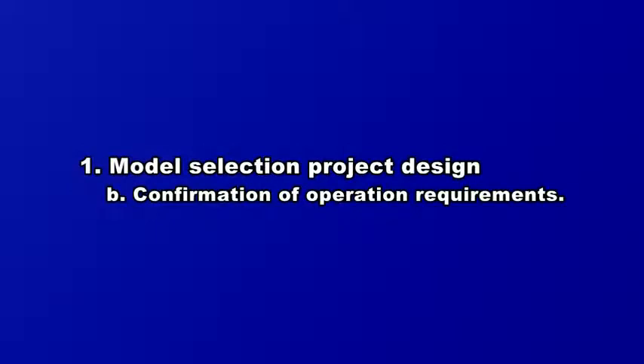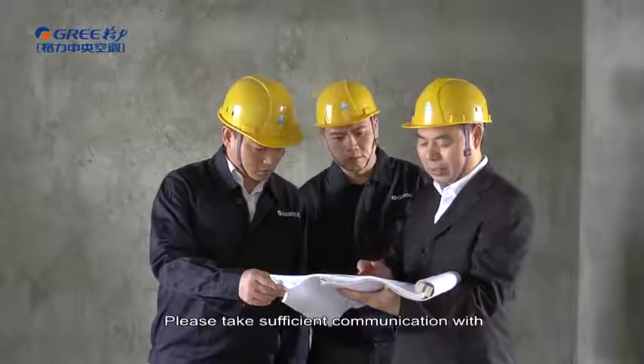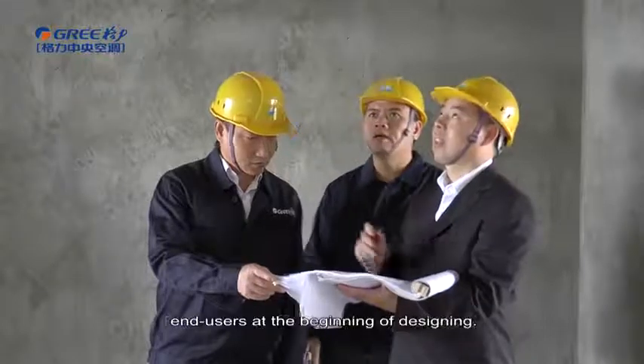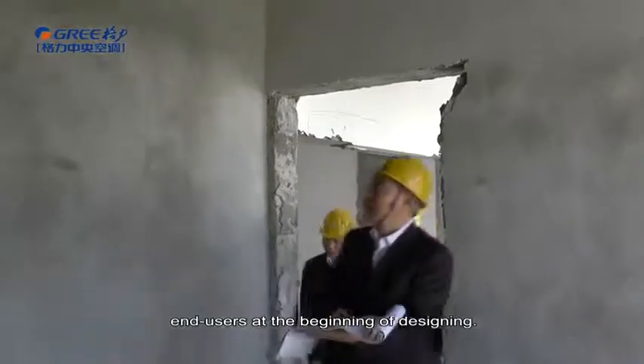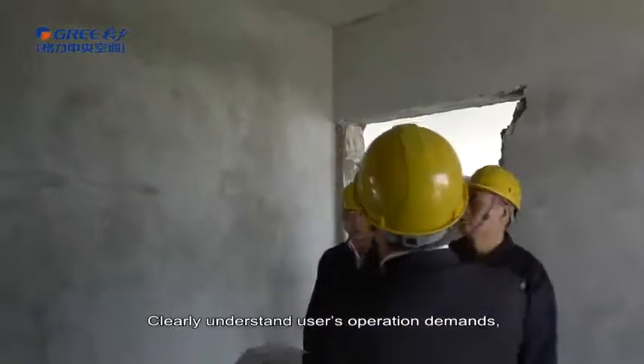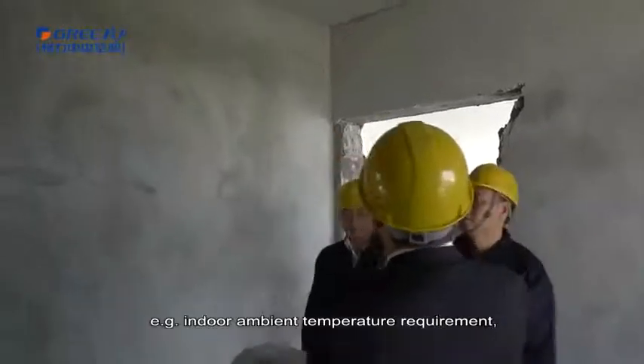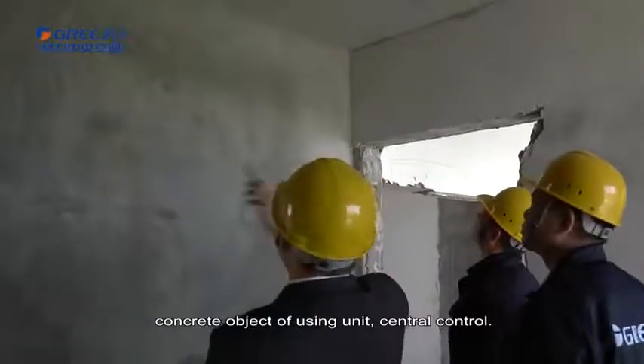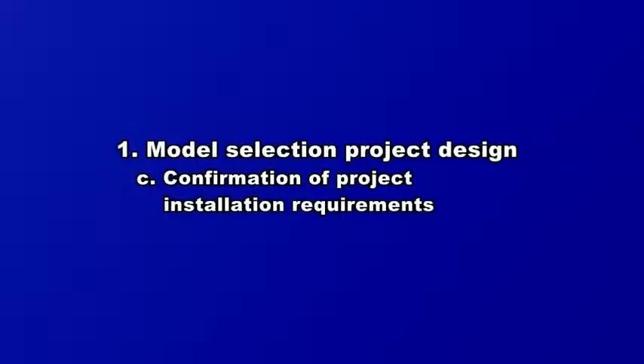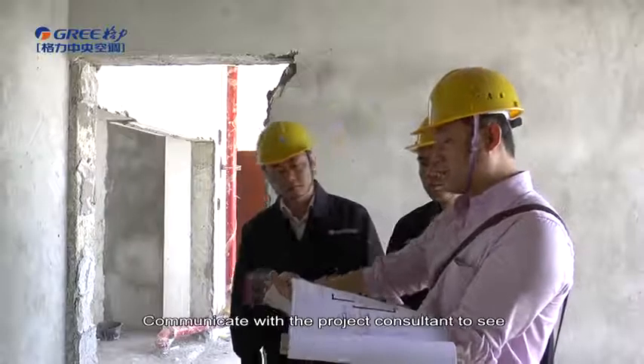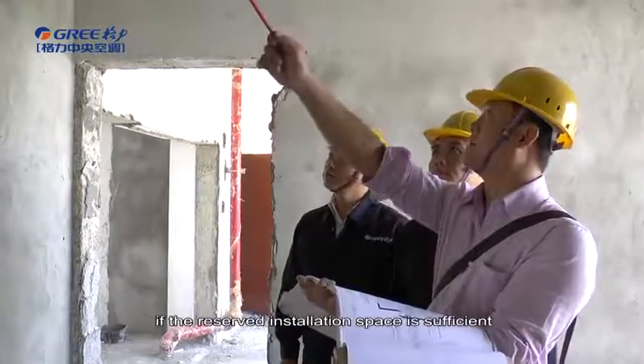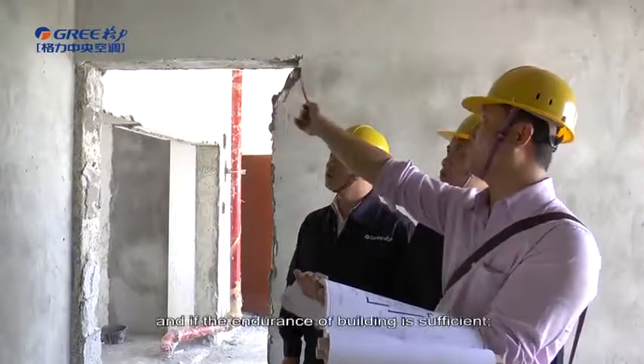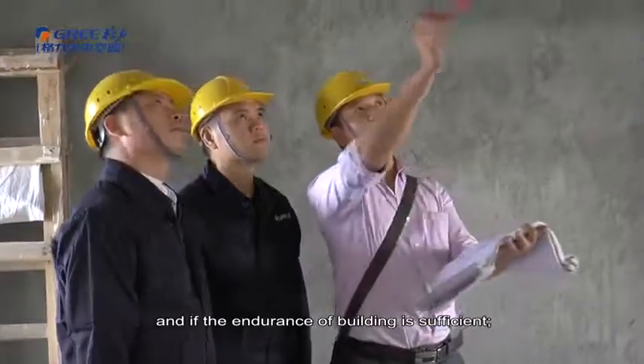B. Confirmation of operation requirements. Please take sufficient communication with end users at the beginning of designing. Clearly understand users' operation demands, for example, indoor ambient temperature requirement, concrete object of using the unit, central control. C. Confirmation of project installation requirements. Communicate with the project consultant to see if the reserved installation space is sufficient and if the endurance of building is sufficient.